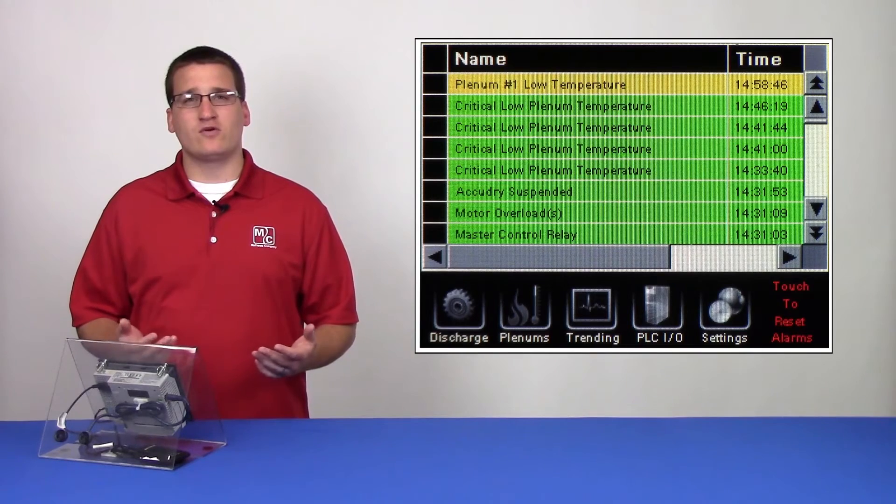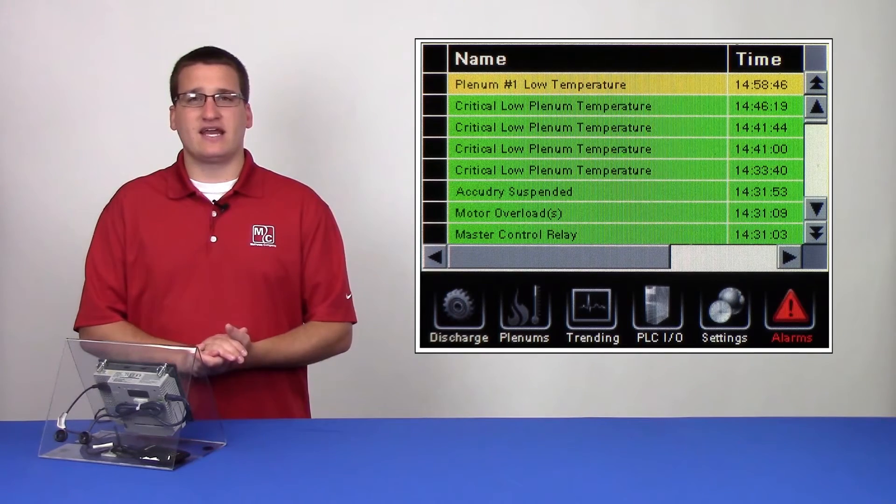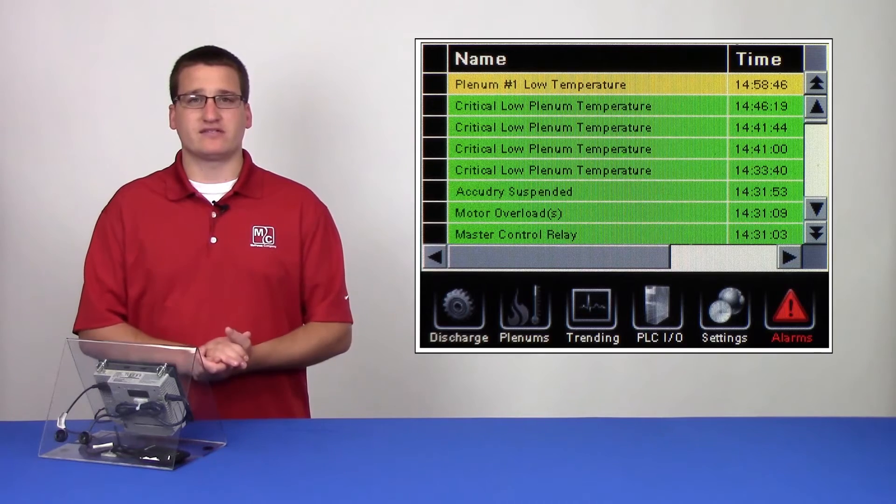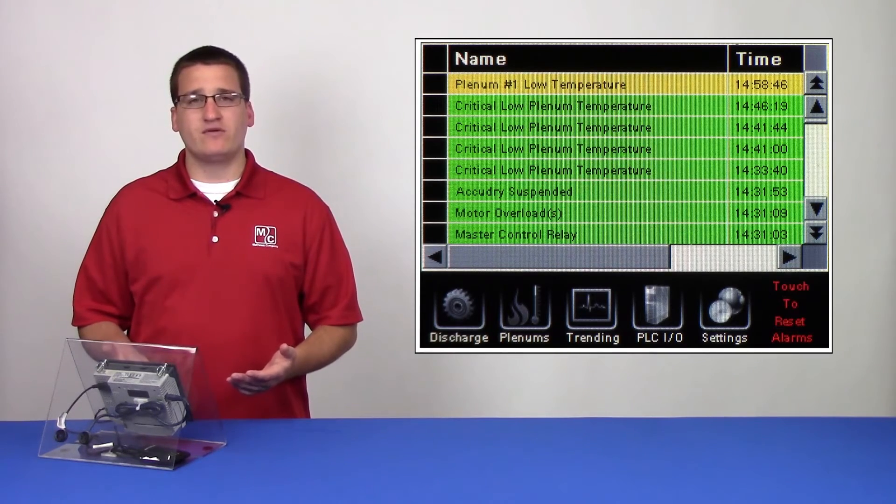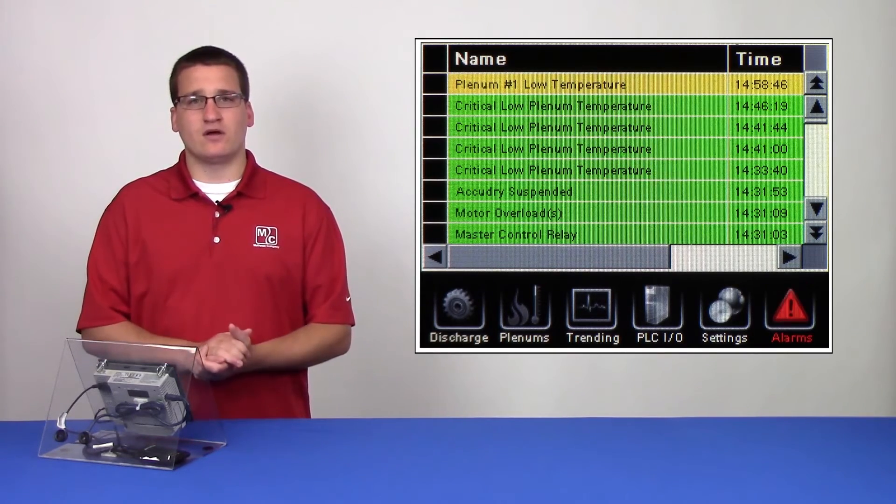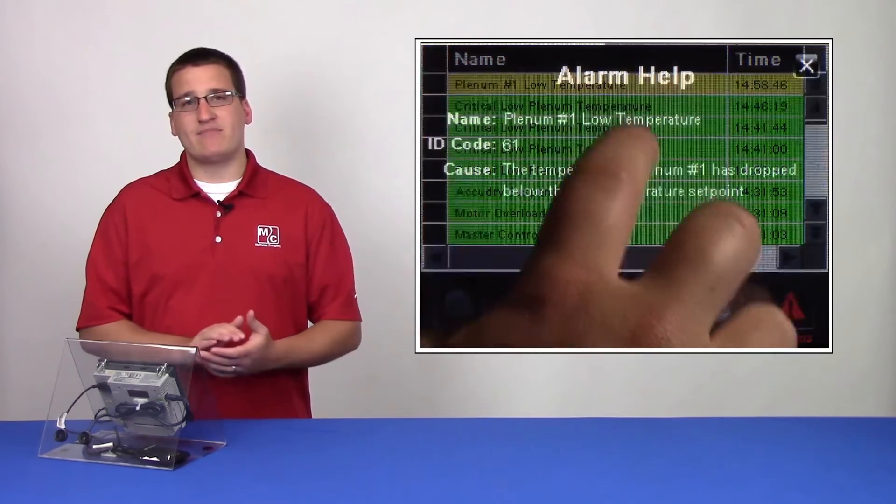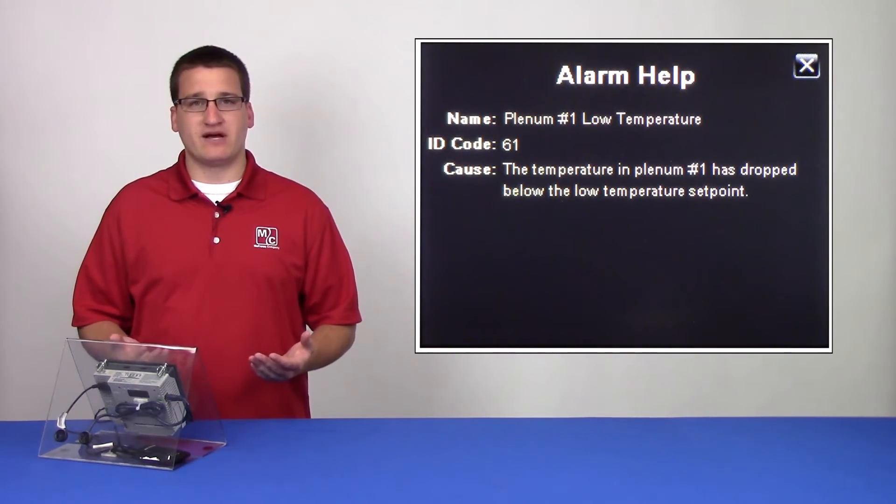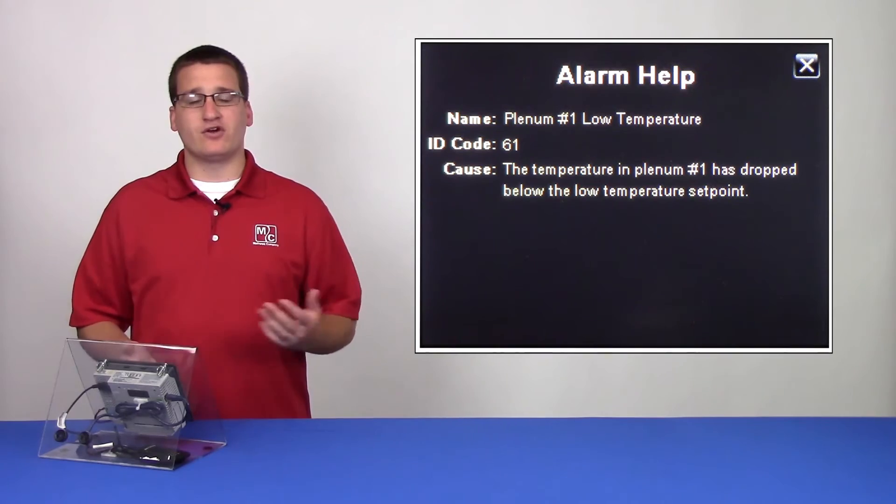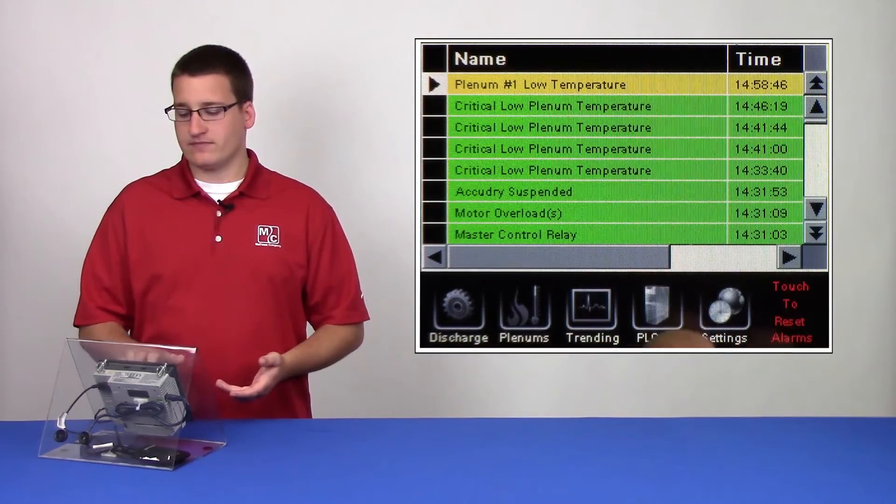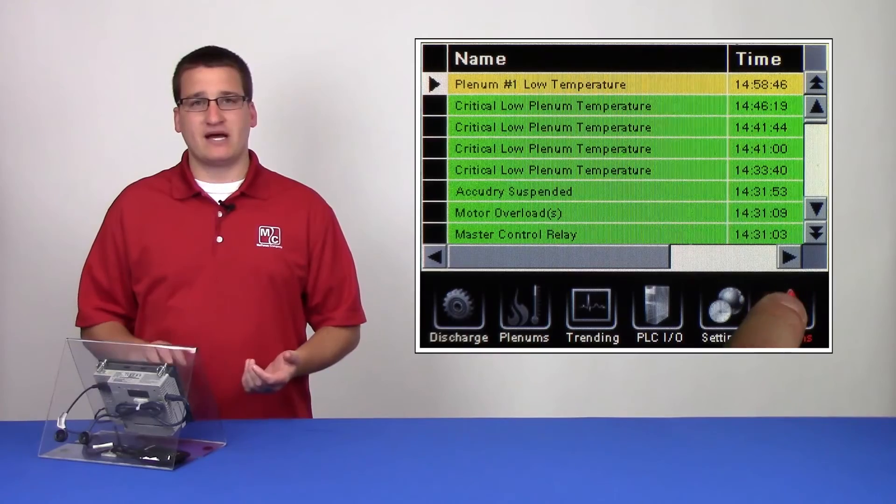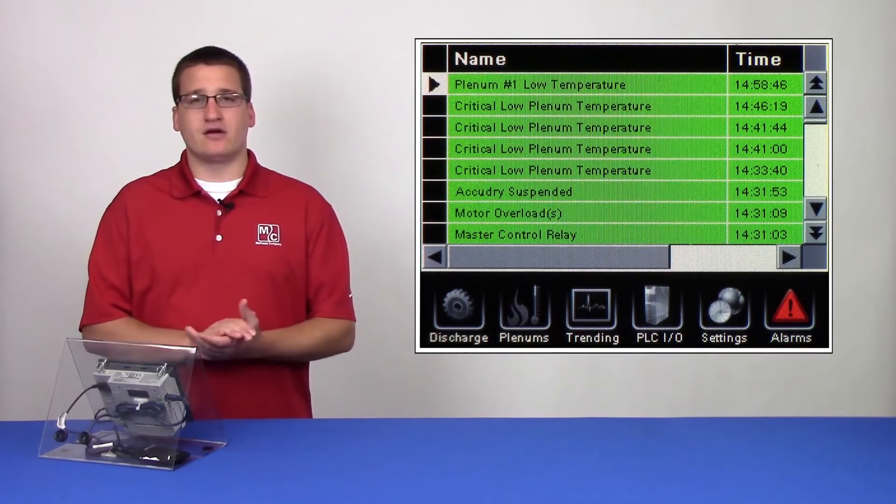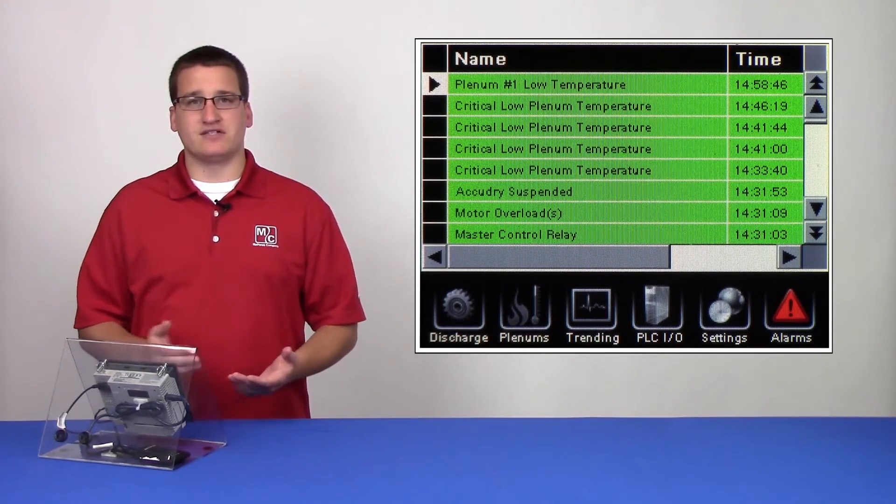If you have a yellow or a red alarm, that indicates a currently active alarm that must be fixed. In our example, we can see that we have one yellow alarm. We can tap on the line to get more information about the alarm. We would then go and address the issue that's described, and then come back to the HMI and double tap the alarms page in order to acknowledge the alarm.